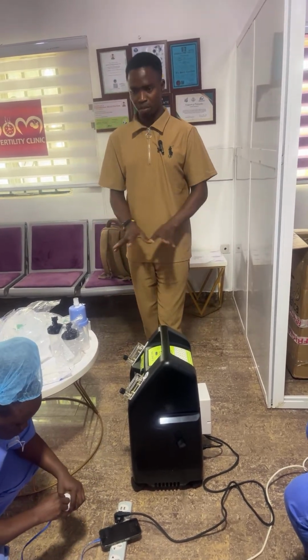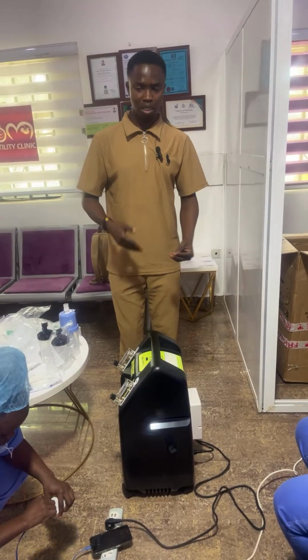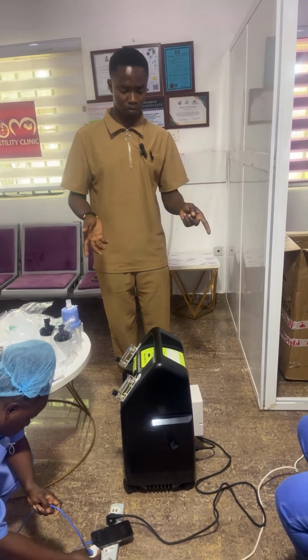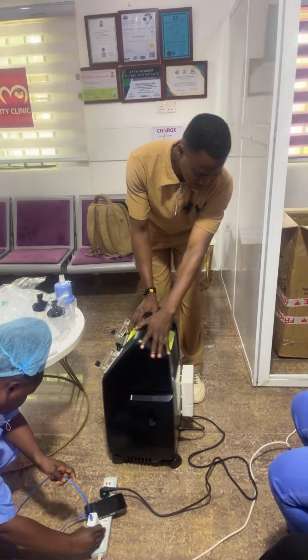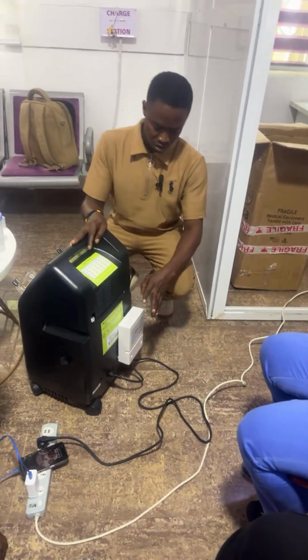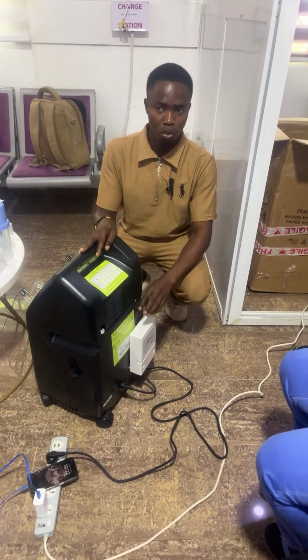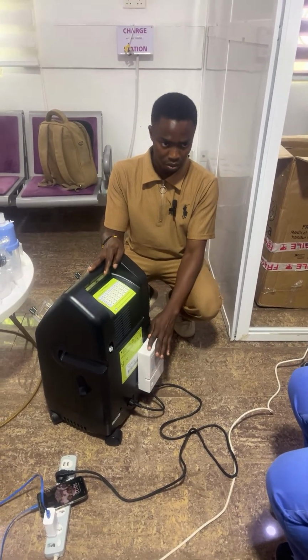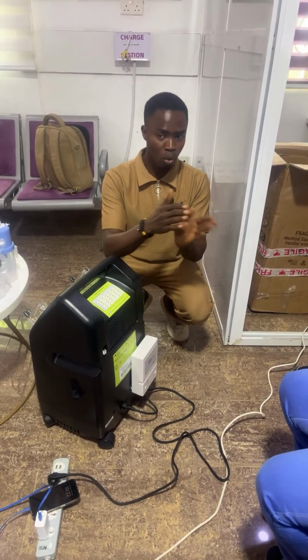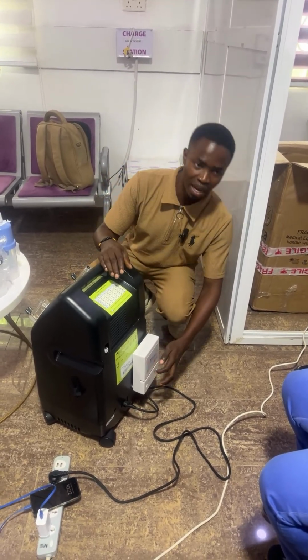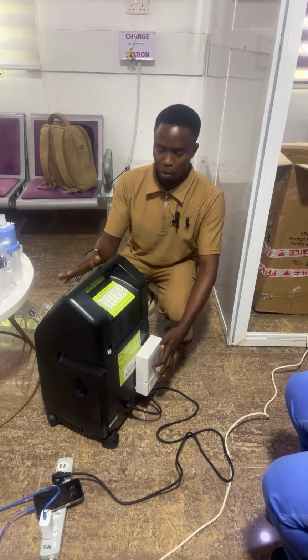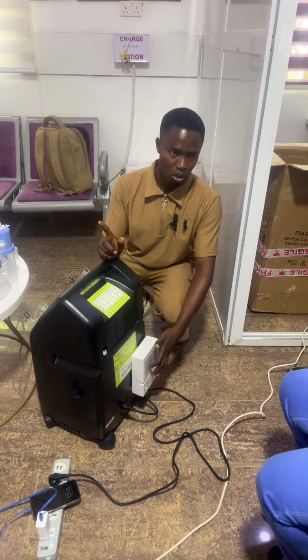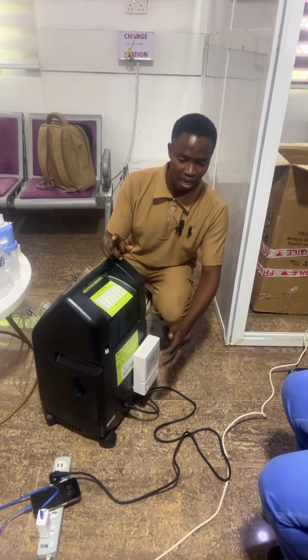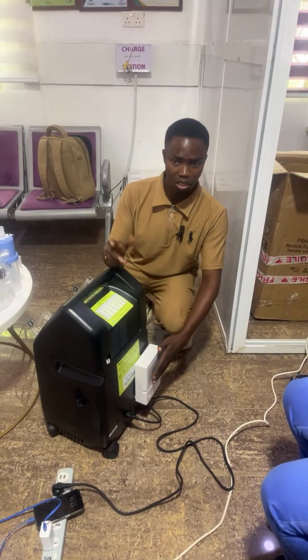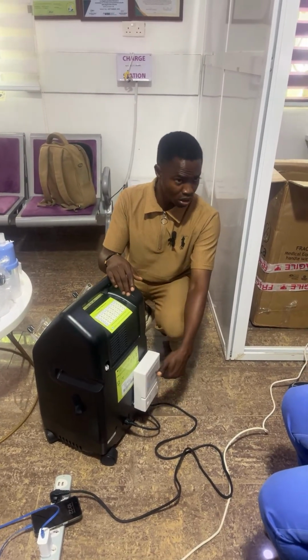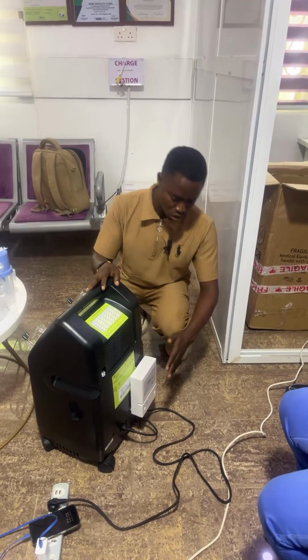But first, let's go through the machine and the parts, so that if you are using it, I can tell you what this is and the function of this. First of all, this is the machine. This is the surge protector, and it's important that I tell you how this works. Electricity comes here. If your electricity is bad, that means too high or too low, this will show either red or yellow. If you power this machine on, it will not come on. You have to wait till it turns green. So anytime you are using it and it's red, check maybe the light is low or it's not properly plugged in before you say it's not working. So it will turn green.